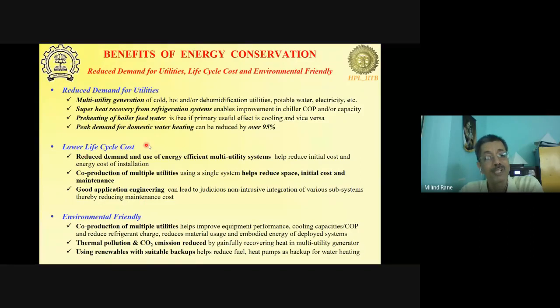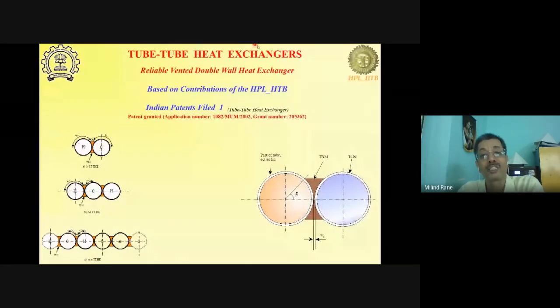So life cycle cost reduction is possible using multi-utility heat pumps, and they are environment friendly because you are generating multiple utilities using a single system. Fewer systems need to be maintained, there are fewer emissions because less refrigerant is being used, and so on and so forth. And renewables can be backed up with these kinds of multi-utility generators. So this is about the tube heat exchanger.